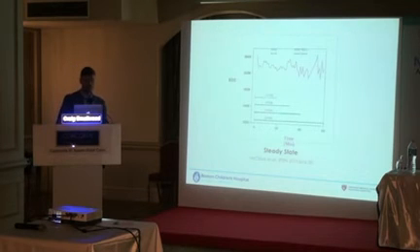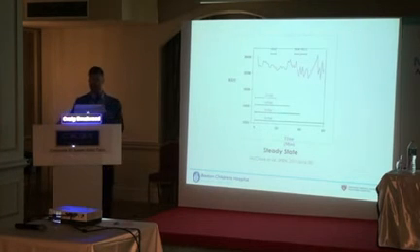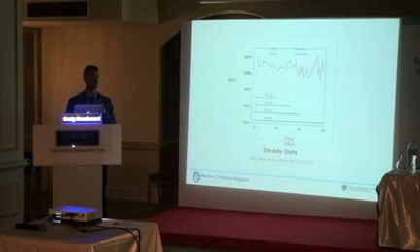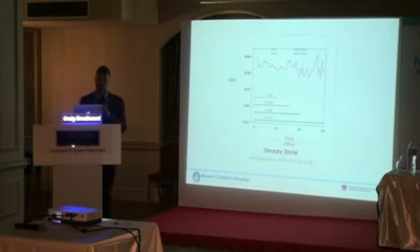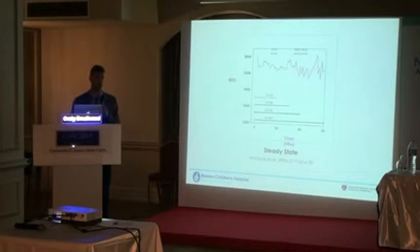So another really important feature of gas exchange and indirect calorimetry is steady state determination. If you've ever seen an indirect calorimeter set up, it's essentially a snapshot. These devices weren't necessarily meant to work for long periods of time, but our patients are living and breathing and burning energy 100% of the time. So we needed a methodology essentially to take a snapshot, about a 30-minute window, and make sure that that 30-minute snapshot reflected what the patient is doing for a full 24 hours. That's one of the important metrics of IC.